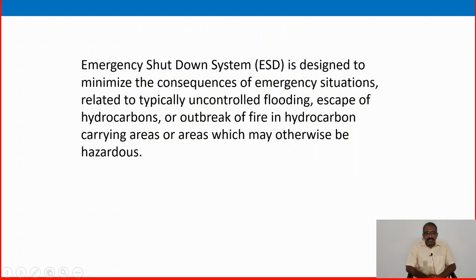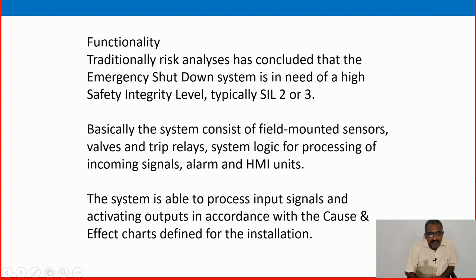The emergency shutdown system is designed to minimize the consequences of emergency situations related to typically uncontrolled flooding, escaping of hydrocarbons, or outbreak of fire in hydrocarbon-carrying areas which may otherwise be hazardous. Traditionally, risk analysis has concluded that the emergency shutdown system needs a high safety integrity level — typically SIL 2 or 3.